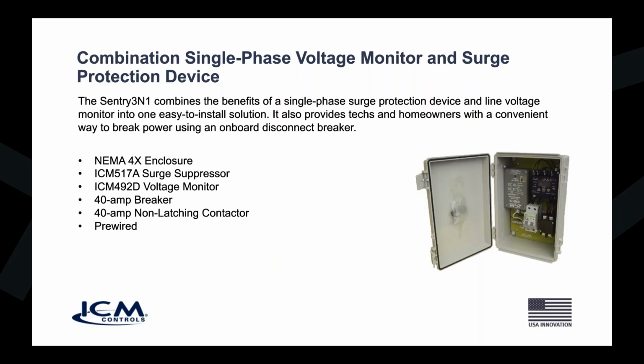The Sentry 3-in-1 combines the benefits of both a single phase surge protective device and a line voltage monitor into one easy solution. And the nice thing about this, it also comes with a convenient disconnect switch built into it. So basically, you can shut power off with convenience without having to disconnect some breaker that may be somewhere else that is inaccessible. Or if you're doing a new install, you don't have to add the additional cost of a breaker, providing that the full load amps of that particular piece of equipment that you're protecting is no more than 40 amps.